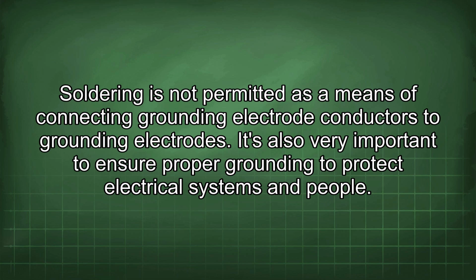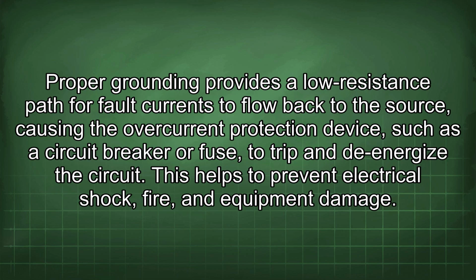It's also very important to ensure proper grounding to protect electrical systems and people. Proper grounding provides a low resistance path for fault currents to flow back to the source, causing the overcurrent protection device, such as a circuit breaker or fuse, to trip and de-energize the circuit. This helps to prevent electrical shock, fire, and equipment damage.